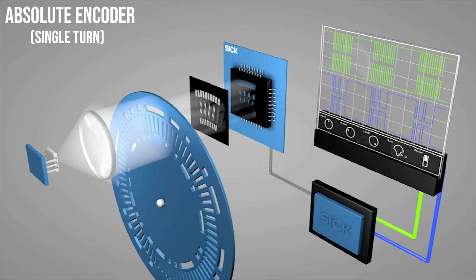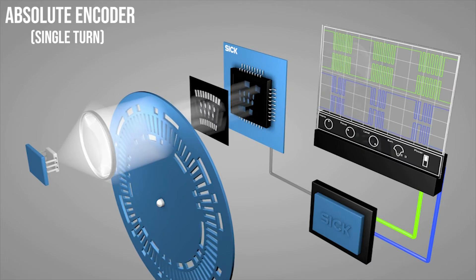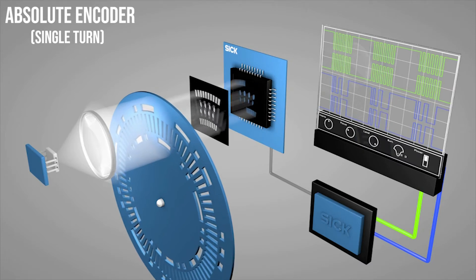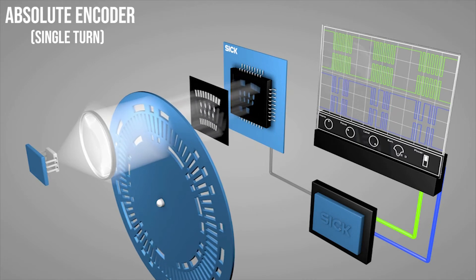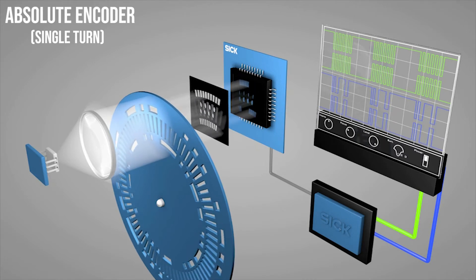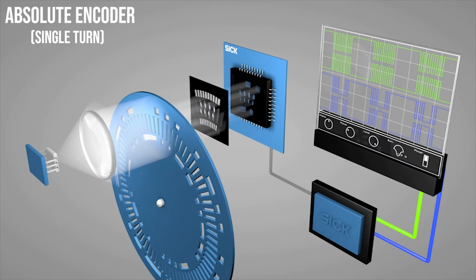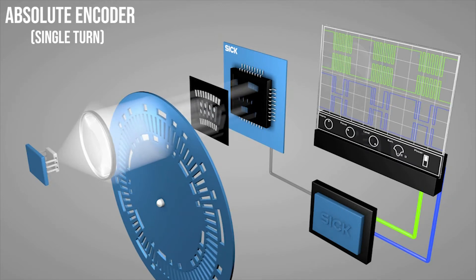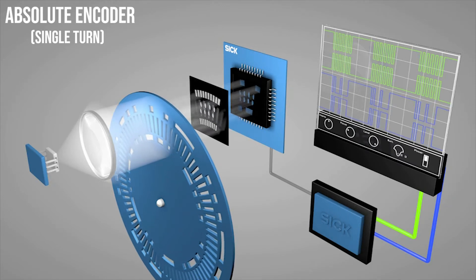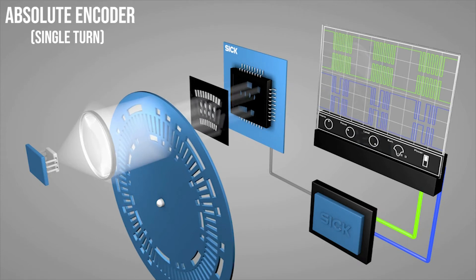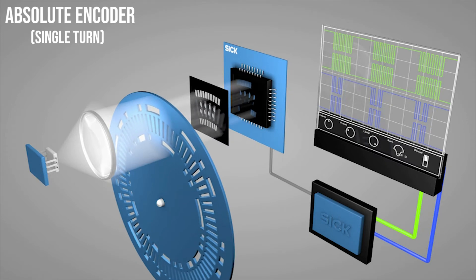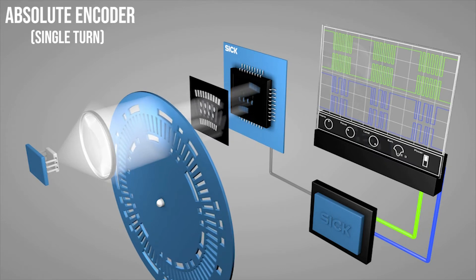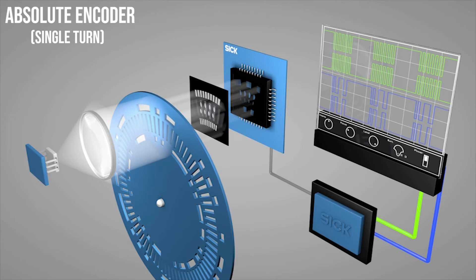This unique address is critical in knowing the exact position of the encoder. The benefit of knowing these addresses is that in the case of a power reset, the home position is not lost. When the encoder powers back up, the light allowed through the disk will always create the same address as it had before the power loss. The encoder is no longer just counting pulses up or down from its home position — it is always knowing exactly where the disk is.